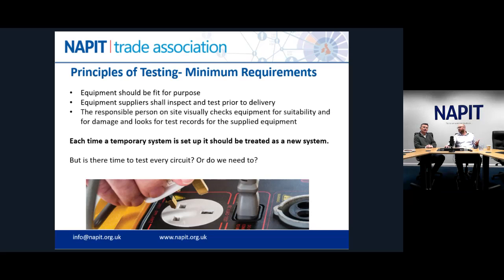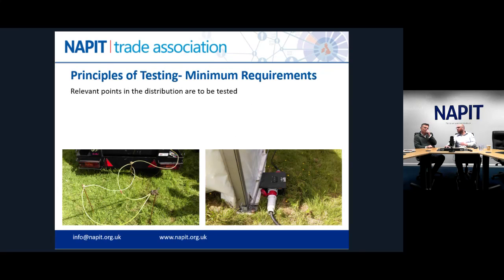Okay. The issue is, do we need to test every circuit? Is there time to test every circuit? No, and I think that will come on. We're gonna wait till the next slide. We're gonna zip through some of the requirements for testing. So BS 7909. Easy for me to say. It gives requirements and it talks about some of the basic principles that are required. Okay. And so, yeah, as you've got here, generator earth electrodes.